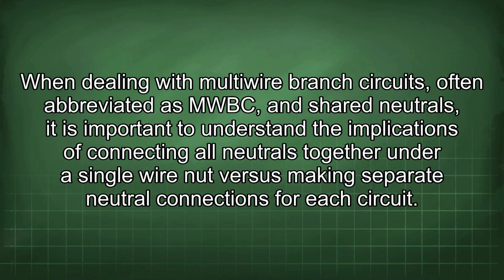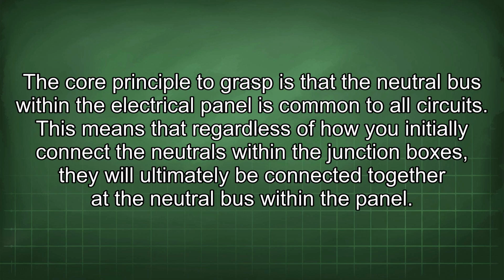When dealing with multi-wire branch circuits, often abbreviated as MWBC, and shared neutrals, it is important to understand the implications of connecting all neutrals together under a single wire nut versus making separate neutral connections for each circuit. The core principle to grasp is that the neutral bus within the electrical panel is common to all circuits. This means that regardless of how you initially connect the neutrals within the junction boxes, they will ultimately be connected together at the neutral bus within the panel.